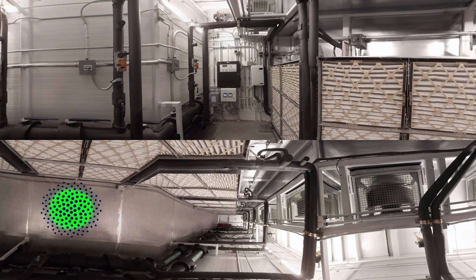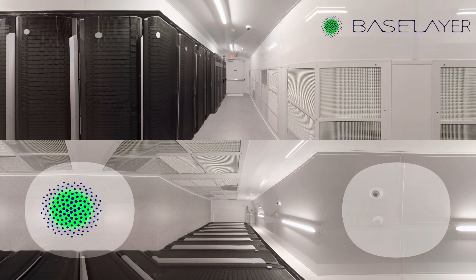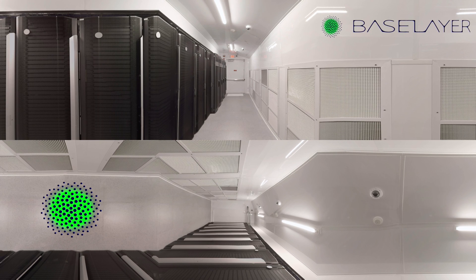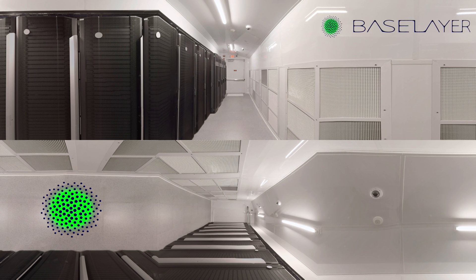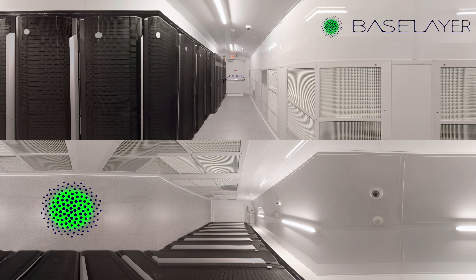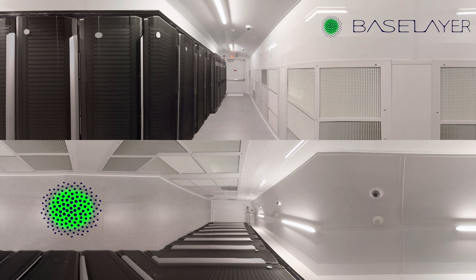Let's move on to the next step and see how the cooling block works with the IT block. You're now standing inside the cooling aisle of the IT block. The XC-10 has an IT block which allows for 20 standardized 24-inch racks, 52U in height. The cold aisle has a wide four-foot door that supports up to 4,500 pounds of roll-in, roll-out equipment weight. Also, notice the well-illuminated workspace and convenience outlets, which enable data center operators and IT professionals an ideal workspace.